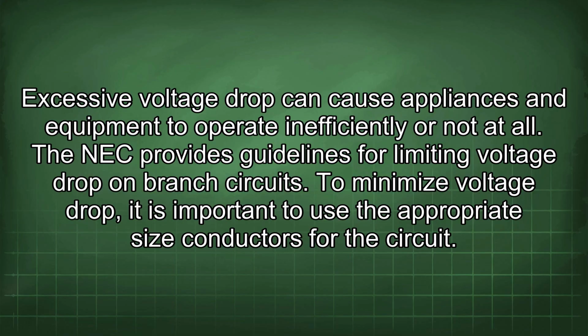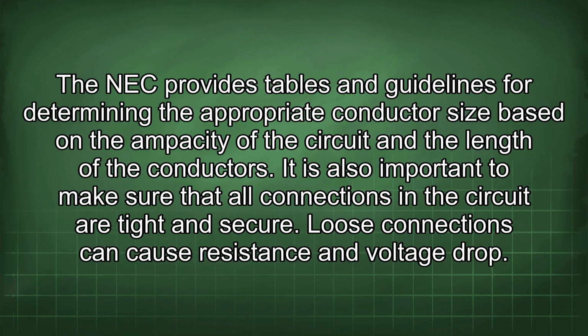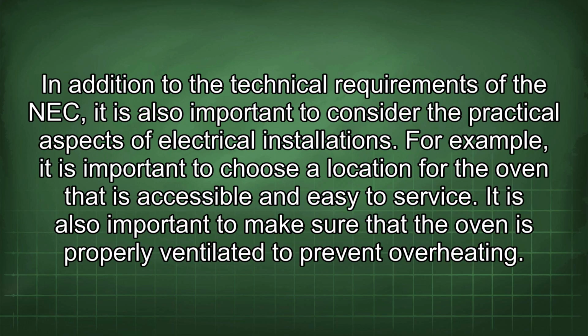To minimize voltage drop, it is important to use the appropriate size conductors for the circuit. The NEC provides tables and guidelines for determining the appropriate conductor size based on the ampacity of the circuit and the length of the conductors. It is also important to make sure that all connections in the circuit are tight and secure. Loose connections can cause resistance and voltage drop. In addition to the technical requirements of the NEC, it is also important to consider the practical aspects of electrical installations.